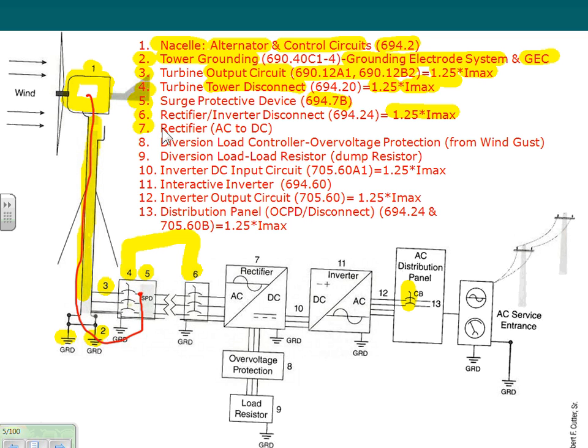Number 7 obviously is going to be the rectifier. Because the voltage you can get over here is out of whack, they take whatever AC you get and convert it to DC. This is typical in a lot of systems where we cannot control the speed of the turbine. With a diesel engine, we can control the speed of the turbine, and so the speed and the frequency. We have no control over Mother Earth's wind. You can't control the speed, so you can't control the frequency. So the easiest way is to take whatever frequency and voltage you get, convert it into one line, DC, we love DC, and then invert it back at the right voltage and the right frequency. And here's my inverter right now, giving a nice sinusoidal wave. So what's the rectifier? Taking the junk AC into DC and smoothing it. So that's my rectifier.